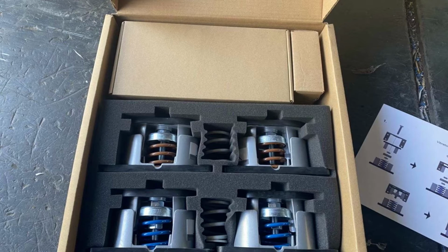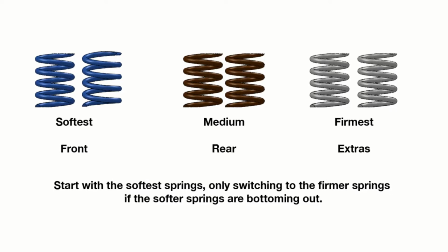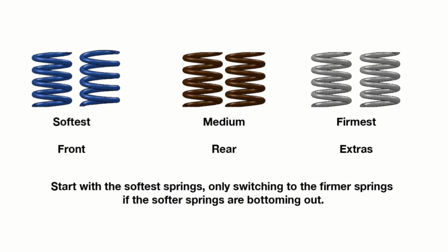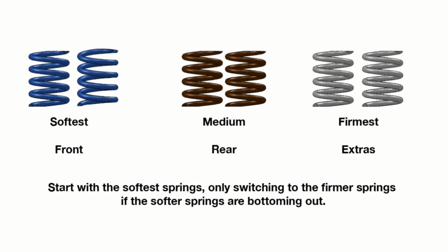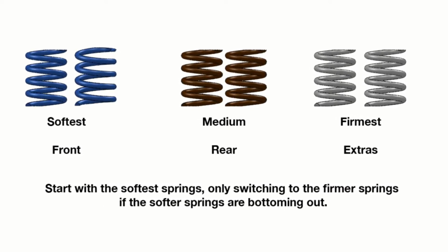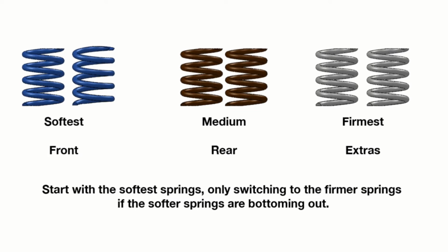Starting with the vibration isolators, their springs have a number of parameters like spring rate, deflection rate, natural frequency, but we figured that out, so you just have to make sure to use the lightest springs that won't bottom out. The kit has three sets of springs, and you want to use the ones that provide the least resistance to motion, meaning the lightest springs possible. They aren't for tuning the system in any other way.